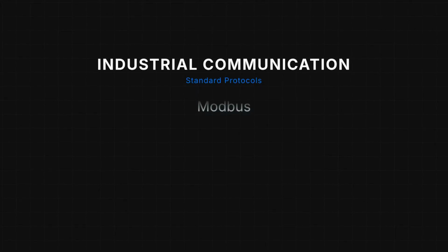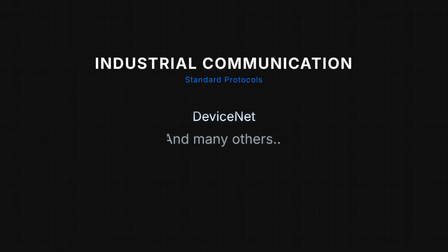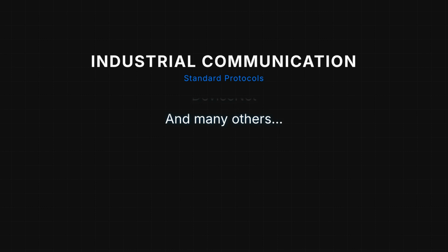Now let's talk about one of the most important concepts in industrial communication: communication protocols. Think of protocols as languages. Imagine you speak Hindi and your friend speaks only Japanese. Communication becomes difficult. Similarly, industrial devices must speak the same language to understand each other. These languages are called communication protocols. Some popular protocols include Modbus, Profinet, Ethernet/IP, Profibus, DeviceNet, and many others. Each protocol defines how information is sent and received between devices. Without a common protocol, communication cannot happen.